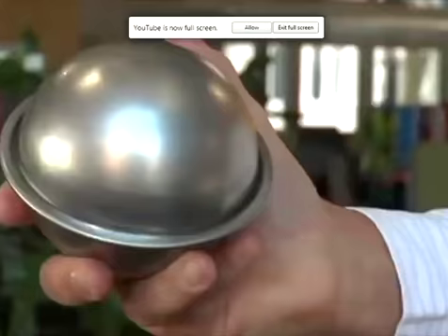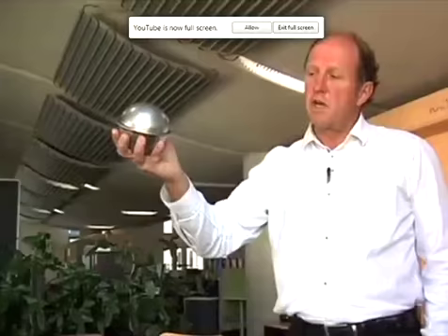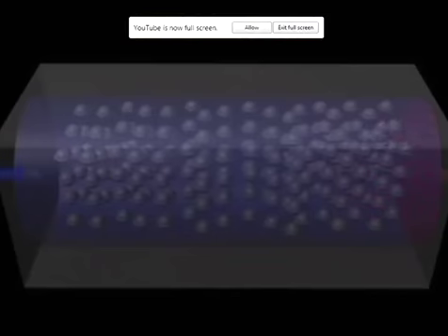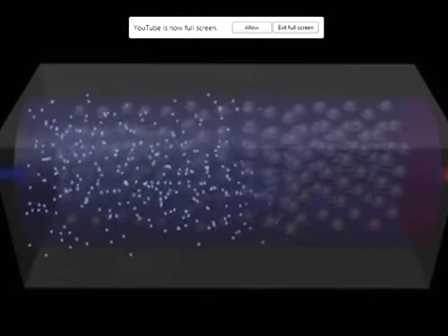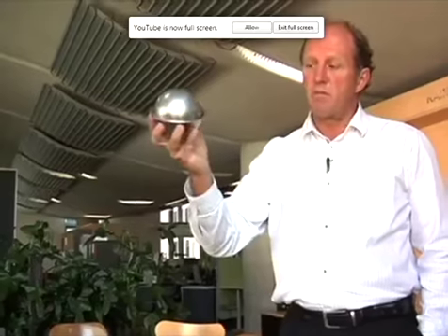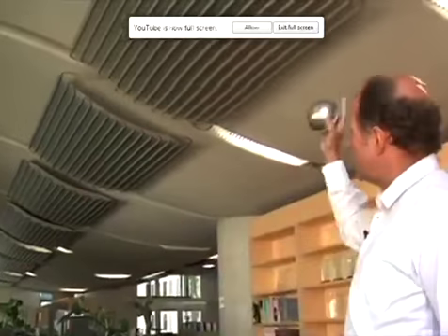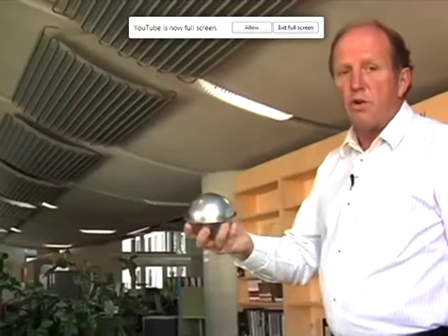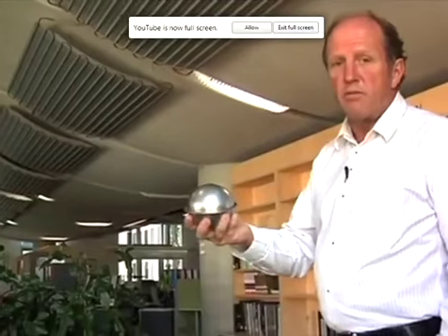In those large tanks we have 10,000 balls, similar to this one, that contain a phase change material. That material freezes at 15 degrees. When we need cool energy back in the building, we then pass the water back over the balls, defrosting them and bringing them into these panels here. The water then drops cool air back into the volume, making the indoor air environment the correct temperature.